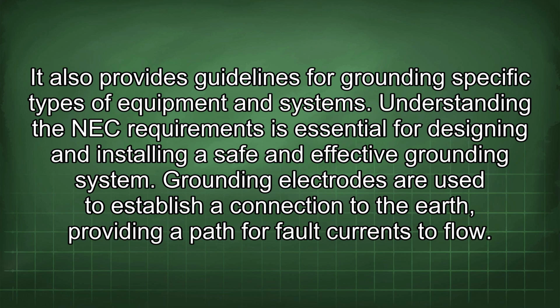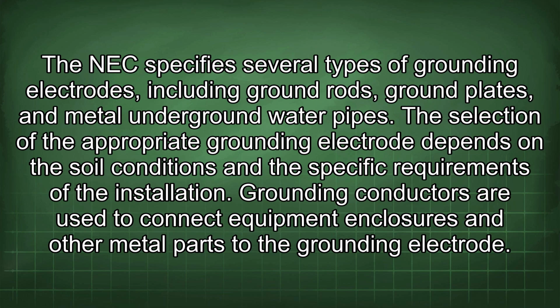Grounding electrodes are used to establish a connection to the earth, providing a path for fault currents to flow. The NEC specifies several types of grounding electrodes, including ground rods, ground plates, and metal underground water pipes. The selection of the appropriate grounding electrode depends on the soil conditions and the specific requirements of the installation.